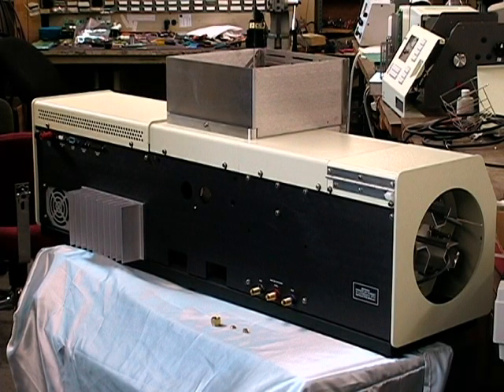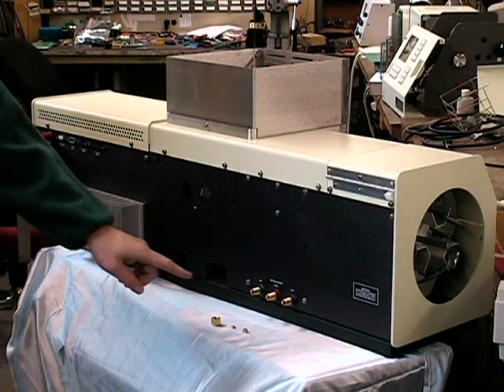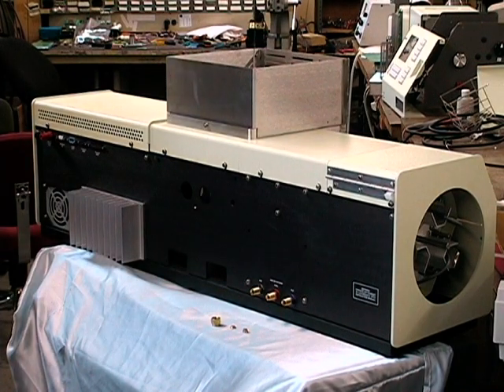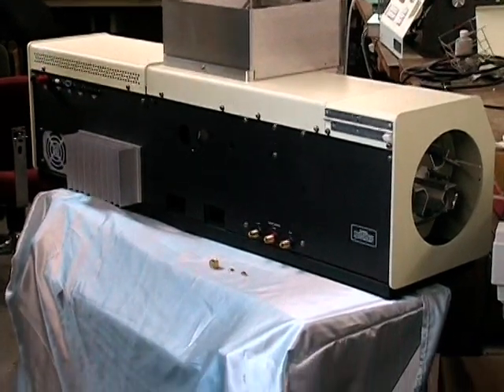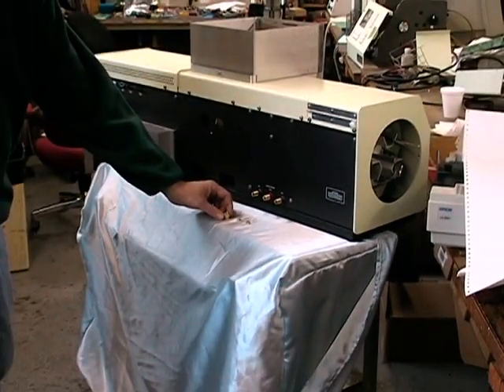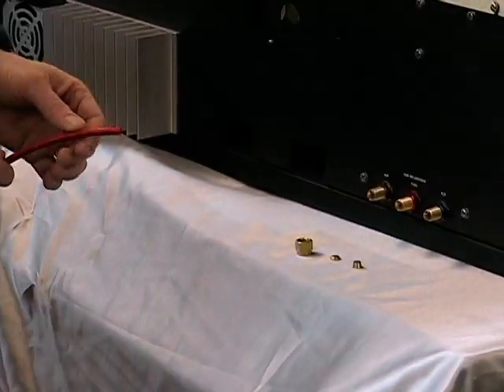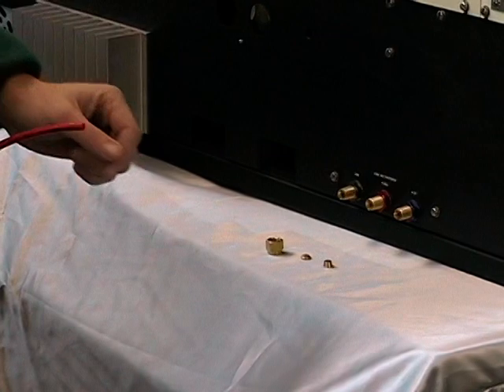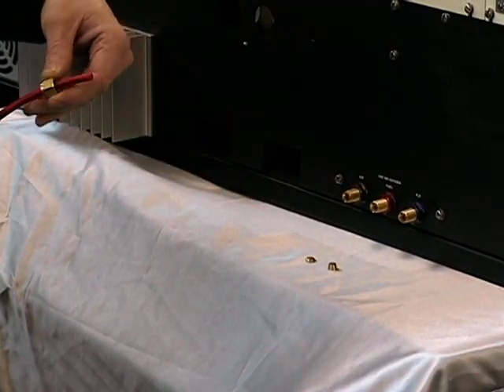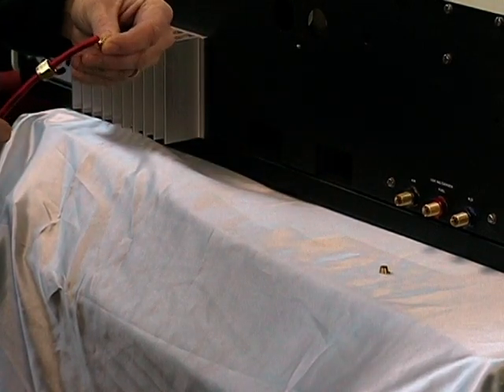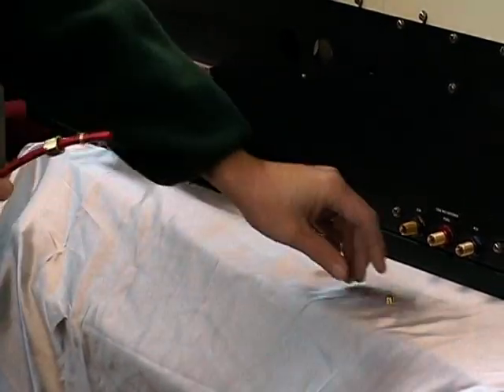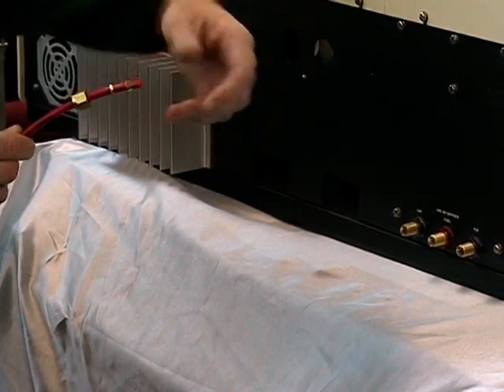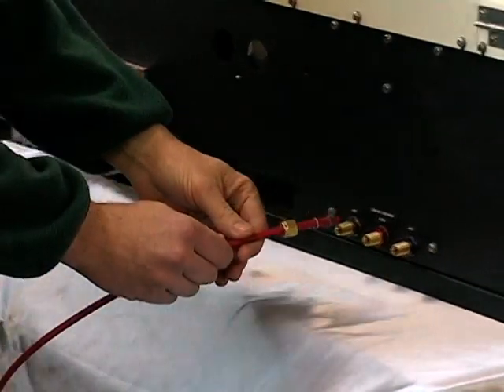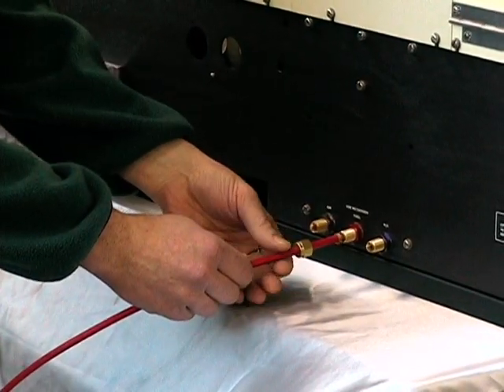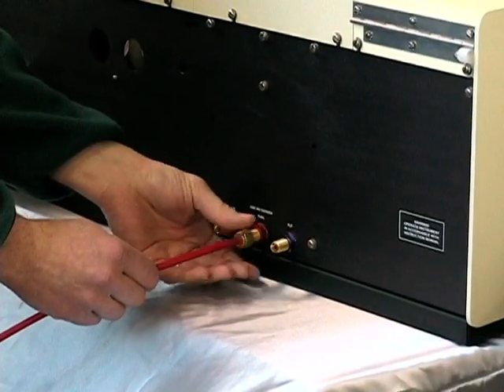The back of your Model 205 AA will have your connections for the electrical power supply and for your gas lines for air, acetylene, and nitrous oxide if used. To prepare a Swagelok gas-tight fitting, make sure that you use the nylon tubing included with the system from Buck Scientific. Make sure the end is cut square, and then place the nut on the end of the tubing first. Then the small donut-shaped ferrule with the narrow end facing out, and then the cone-shaped ferrule, again with the small end facing out. Fully insert the tubing into the fitting, push the ferrules and the nuts forward, and hand tighten as much as possible.